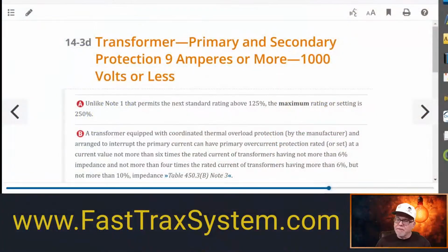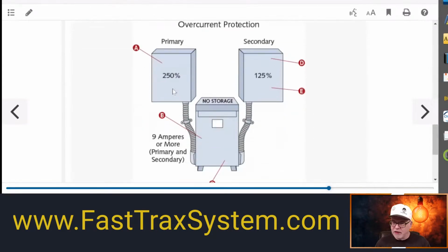Okay, so here we are, and this is still in Unit 14, by the way. This is a case where we're looking at this scenario. People ask me all the time, when is there a scenario when I would go up to 250% on the primary side? Well, I might go up to 250% on the primary side if I'm having trouble with the transformer, if I'm having an issue where I might be supplying multiple secondary loads, multiple panels, and that type of thing that could put a lot of stress onto the transformer, assuming you sized the transformer properly, and all those types of things.